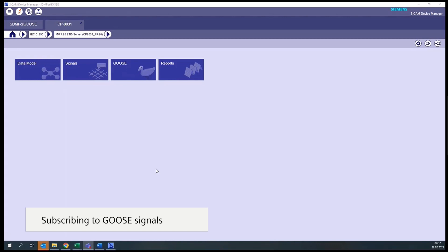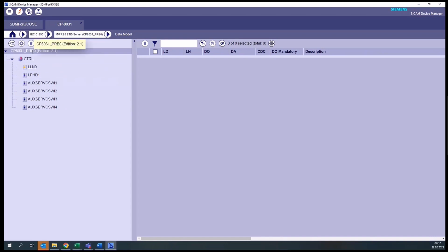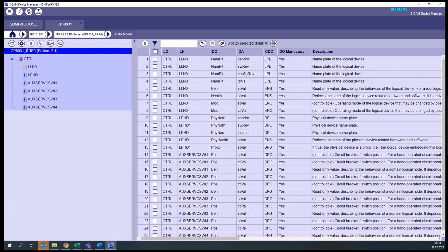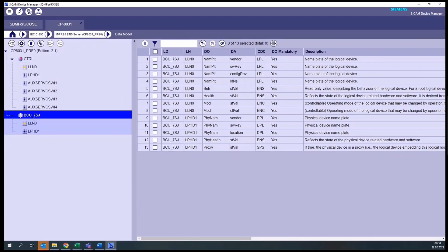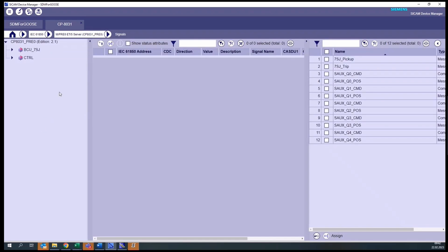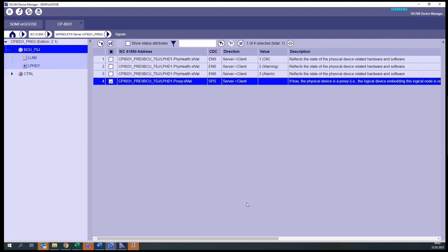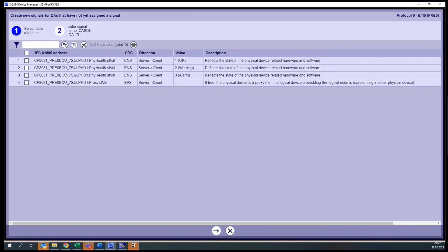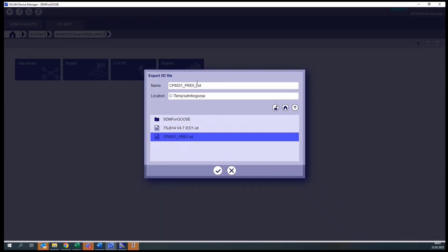Now we will see what we have to do if we want to receive information via GOOSE from another device in the SICAM A8000. First, we expand the data model so we can create a logical device for the connection with the GOOSE messages that we will be receiving. Let's say we will receive some trip information from a protection unit in one bay. This logical device must be included in the data model when we export it from SICAM Device Manager. For that, we need to map at least one process signal to one element of this logical device. We will choose this element and create one new signal to be mapped to it automatically — this trick is just to be able to export the logical device. Now that we have at least one signal in this logical device, we can export the data model again.